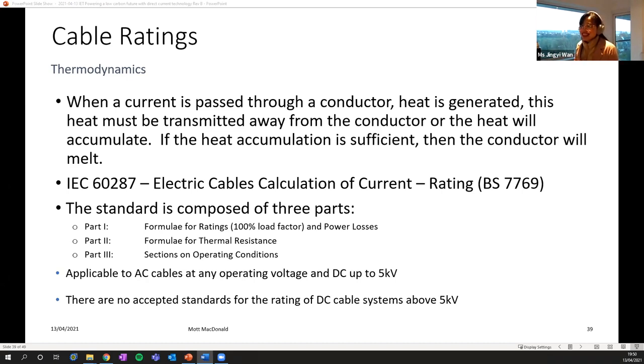The current ratings are calculated according to IEC 60287, and this standard is widely used around the world. This standard comes in three parts, which are listed here. It covers AC cables across the spectrum and only covers DC up to 5 kV. Anything above 5 kV, there isn't a recognized standard for calculating the rating at the current stage, although there are some working groups looking into increasing the voltage coverage. One way of doing the calculation is to reduce the frequency to 1 Hz, which then reduces the reactive component.